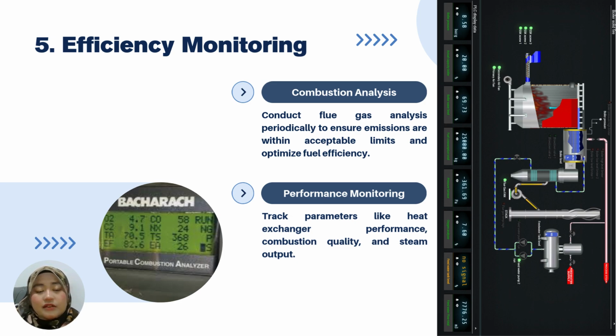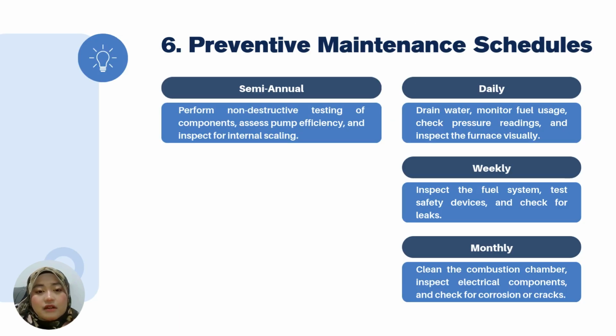Efficiency monitoring involves combustion analysis and also performance monitoring. Combustion analysis is to conduct flue gas analysis periodically to ensure emissions are within acceptable limits and optimize fuel efficiency. Performance monitoring revolves around tracking parameters like heat exchanger performance, combustion quality, and steam output, as you can see in these diagrams. The next maintenance procedure involves preventive maintenance schedules.